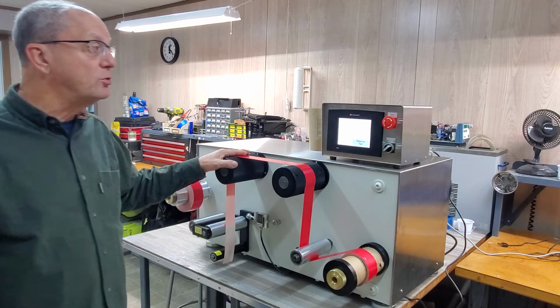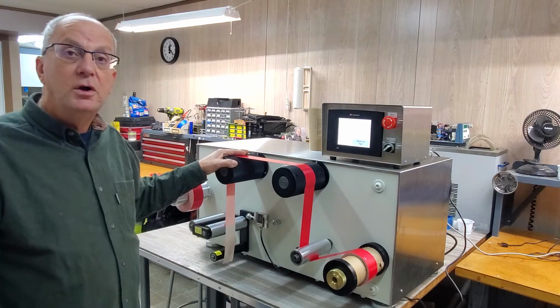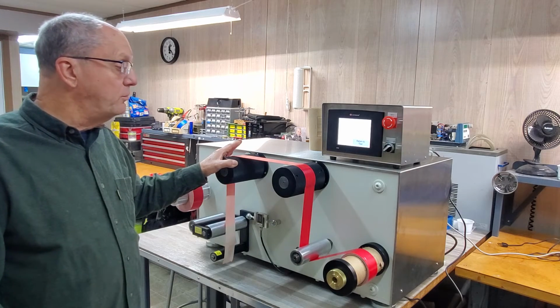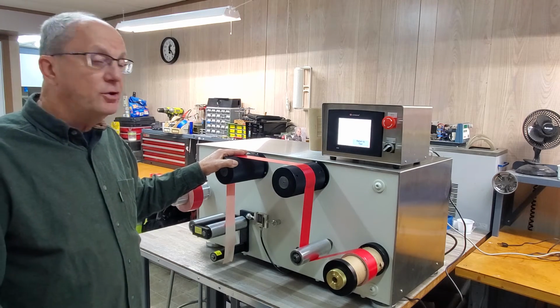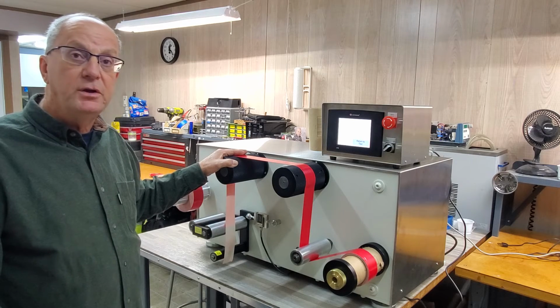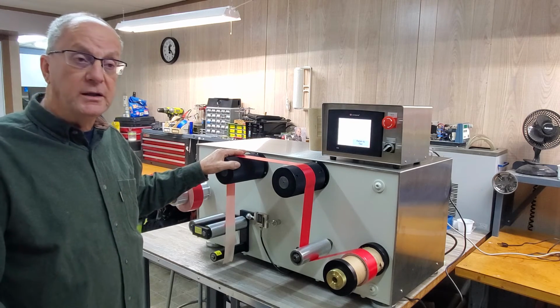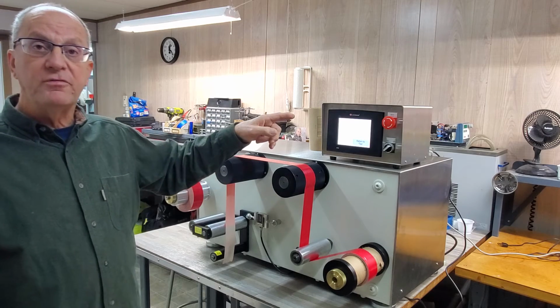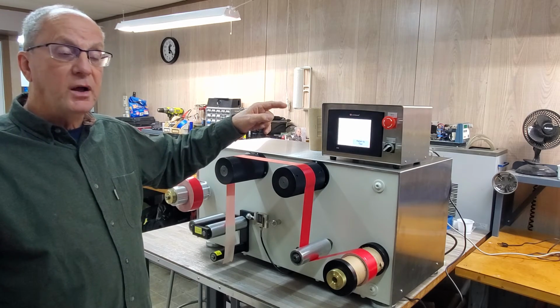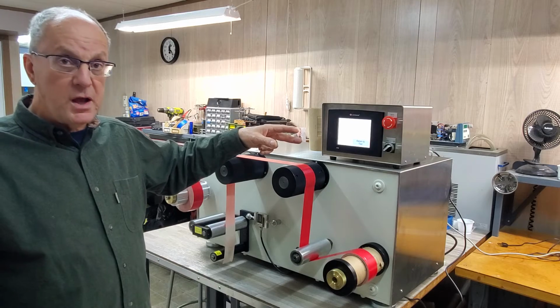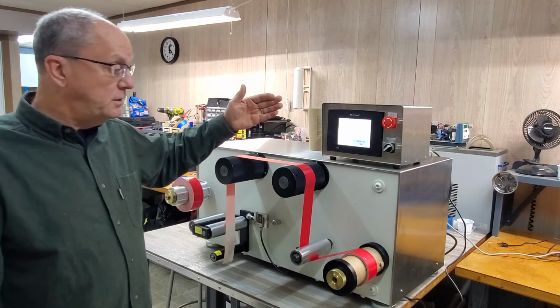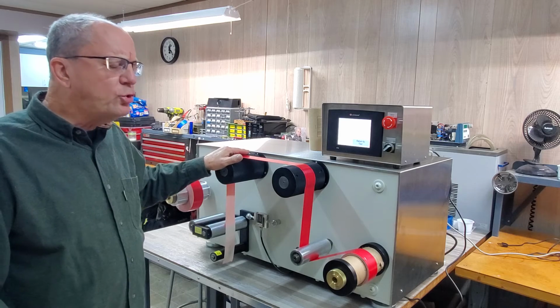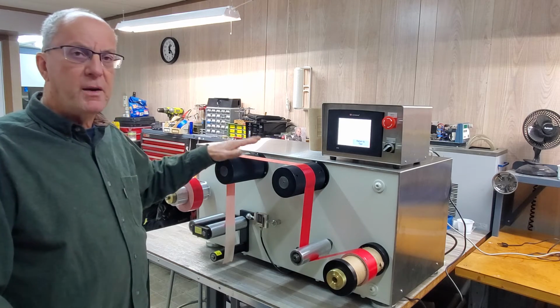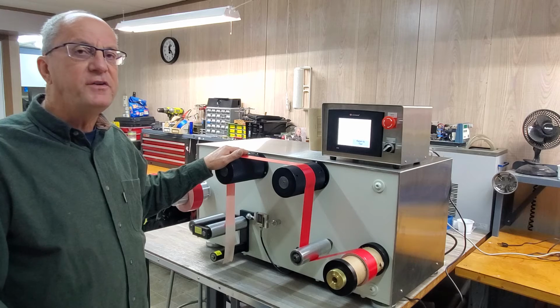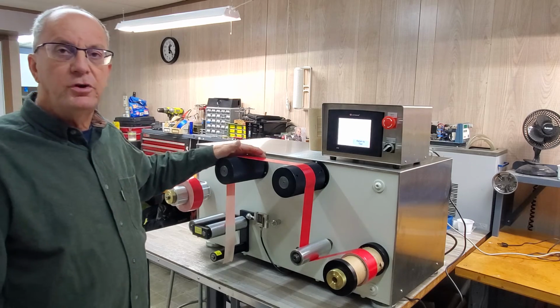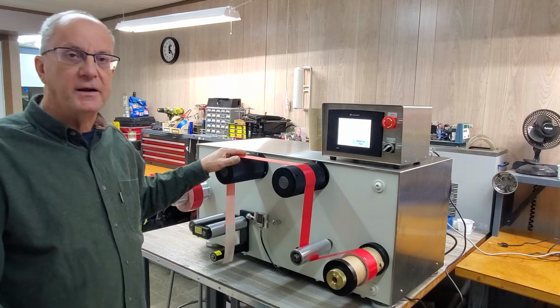What the speed inhibit will do is essentially ignore any data that's measured until this thing gets up to the operating speed, plus or minus whatever number we key in there. For example, if I run it at 150 and I make my speed inhibit plus or minus 5 feet per minute, what's going to happen is this thing's going to ramp up, but until it gets to 145 feet per minute, it's not going to start tallying any of the data.